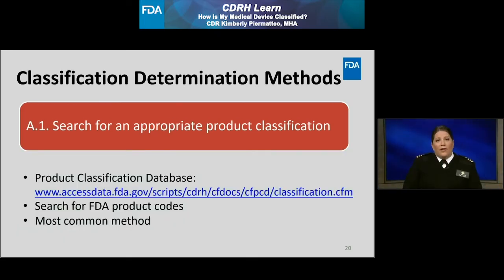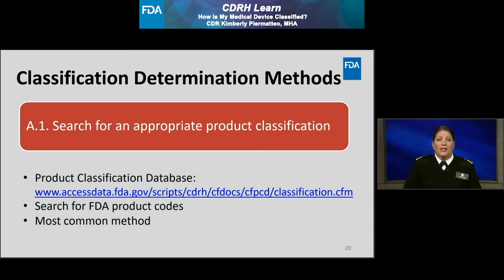The first method I recommend is to search directly for an appropriate product classification in the FDA's Public Product Classification Database. You can search this database to identify an appropriate FDA product code, which then allows you to review the regulatory requirements for that particular device type. This method is the most common and often used.